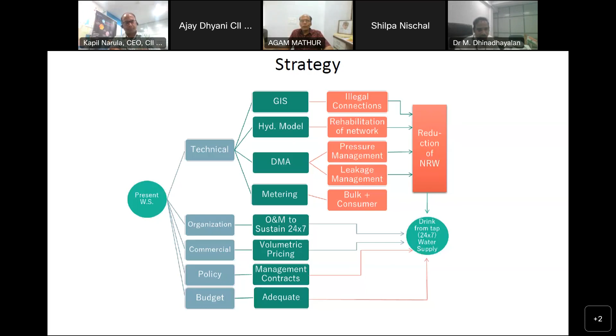So I would like to highlight the salient features of the manual. The concept of drink from tap is brought out. Planning, design, and investigation of the water supply system should be done properly with proper survey. Modern technology of GIS modeling, systematic removal of consumer underground tanks, water to reach the 3rd floor. I explained about pressure. Peak factor, we have recommended 2.5, we eliminated 3 and 2 and all. We have got this figure from the Puri water supply system, which was commissioned in 2021, which is running efficiently. They conducted the peak factor study. Since we are recommending 24/7 water supply, we have considered 2.5 as the peak factor.